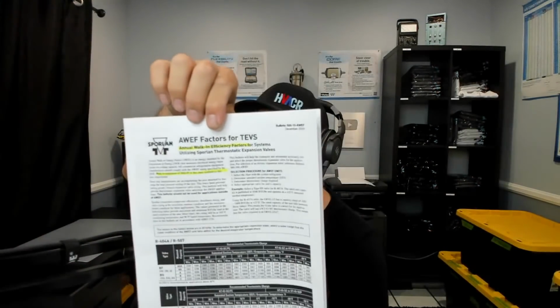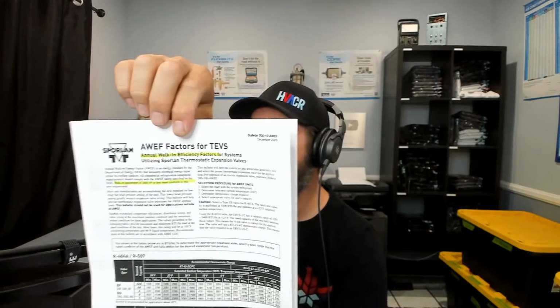If you're swapping condensing units and using existing evaporators, you need to investigate the expansion valve sizing. I talked about it in my recent video, and I'll say it again. Sporlan has a tech document, 500-10-AWEF. You guys can go to the Sporlan, just look up AWEF factors for TEVs, Sporlan, whatever, and it'll help you to size your expansion valves for the new AWEF compliant refrigeration equipment. So understand, you need to make sure that your equipment's sized appropriately, okay?